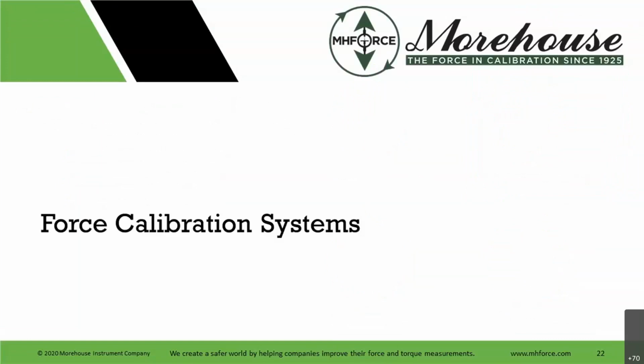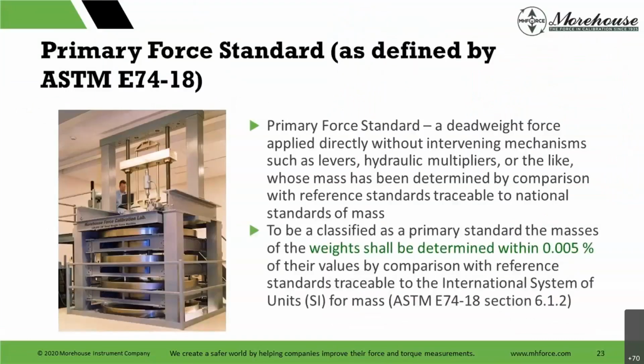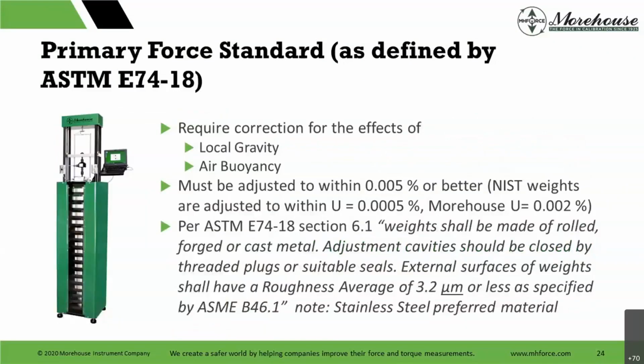Force calibration systems. So we've covered accuracy and uncertainty. I talked a little about ASTM, and I'm going to talk a little more about it for those that don't know. A primary force standard is a deadweight force applied directly without intervening mechanisms such as levers, hydraulic multipliers, or the like, whose mass has been determined by comparison with reference standards traceable to national standards of mass. To be classified as a primary standard, the weights have to be determined within 0.005%. When we talk about force systems and mass weights, they require correction for the effects of local gravity and air buoyancy. And there's a section in E74, 6.1.